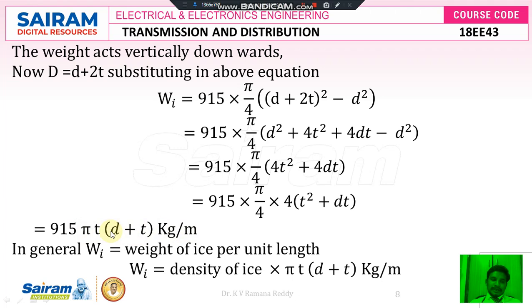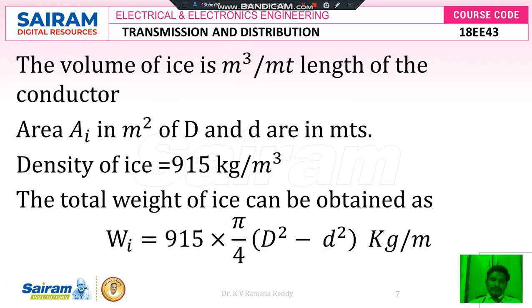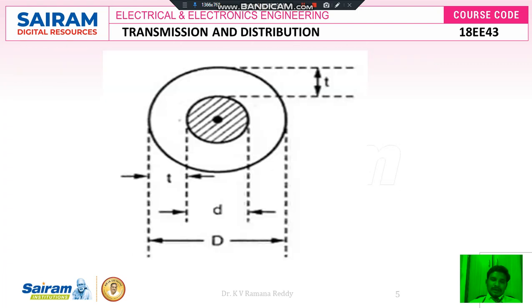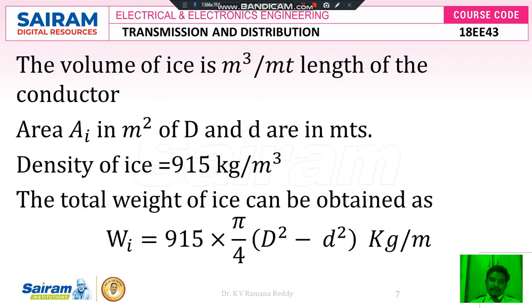Therefore the weight of ice per unit length, Wi, equals the density of ice into π × t × (d + t) kg/m. Substituting the density of ice as 915, the overall formula is: Wi = 915 × π × t × (d + t) kg/m. This is the overall formula for the weight of ice, because ice forms as one layer on top of the surface area of the conductor. Thank you.